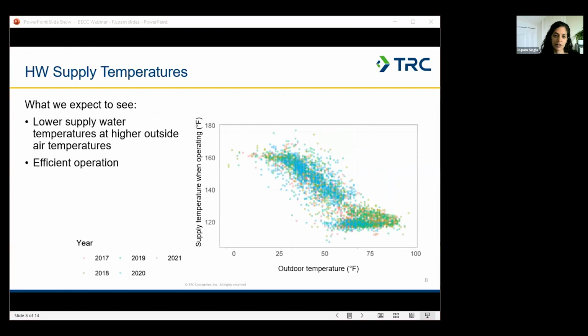So heating hot water systems generally operate much more efficiently at lower hot water supply temperatures. So we only want the water to be as hot as is needed to meet heating requirements. Because at lower supply water temperatures, we have less distribution losses, and heating equipment tends to operate more efficiently at the lower supply water temperatures.